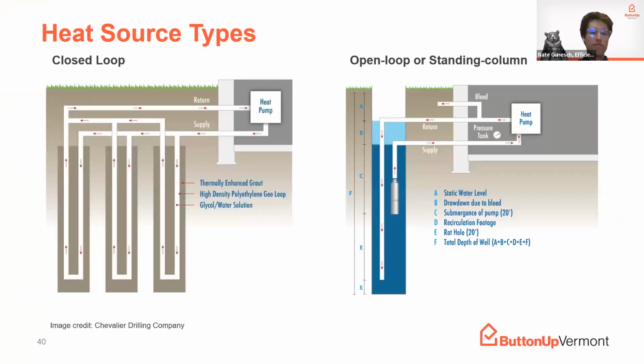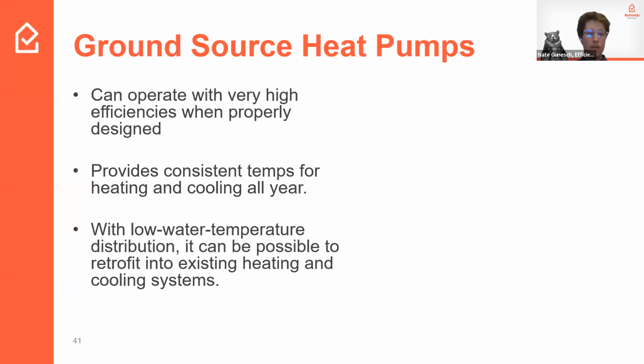There are a couple different types of ground source heat pumps. Closed loop systems typically run a glycol-water mix through closed pipes, using the ground as a thermal battery and conducting heat through the pipe edges. Open loop systems draw directly from the water below the ground. We see a lot more closed loop systems in Vermont, and they tend to be very reliable. If you have questions about the differences, give Efficiency Vermont a call and we can talk through that. But most of what we see are closed loop systems.